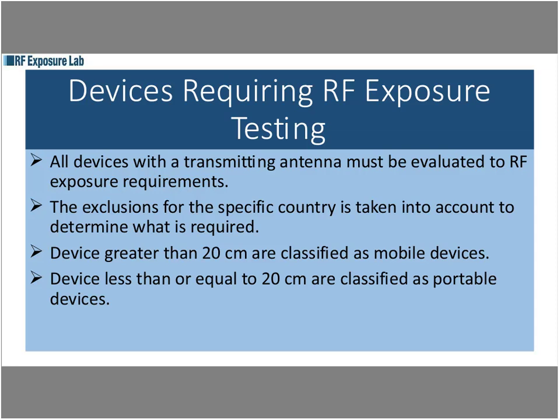There are exclusions for specific countries that can be taken into account to determine what is required. The FCC has a formula to determine whether you have to do a test on a specific device. It's based on the transmit power, the frequency, and the distance the device is from the body. Europe has just a single number. Anything over 20 milliwatts, they want a SAR report. Anything under 20 milliwatts, they don't require a SAR report. Industry Canada recently, with RSS 102 issue 5 coming out, completely changed their direction, their numbers. They have specific numbers, and then you just interpolate in between based on distance. Their numbers are much more conservative than the FCC's, so quite often you may not have to do testing for the FCC, but you might still have to do testing for Industry Canada.